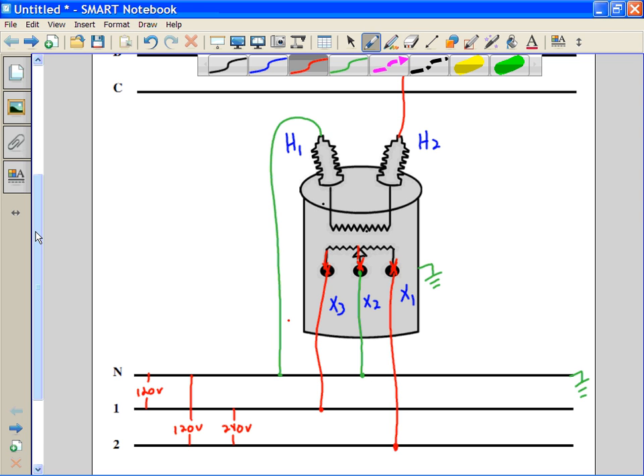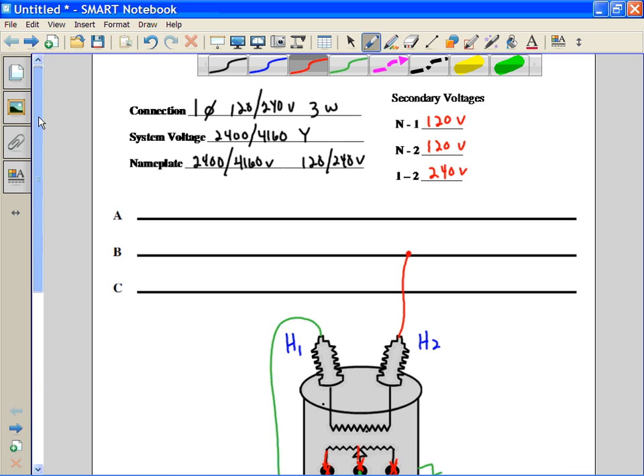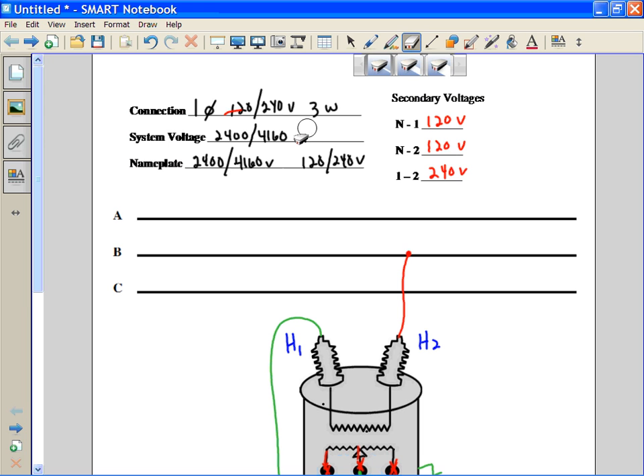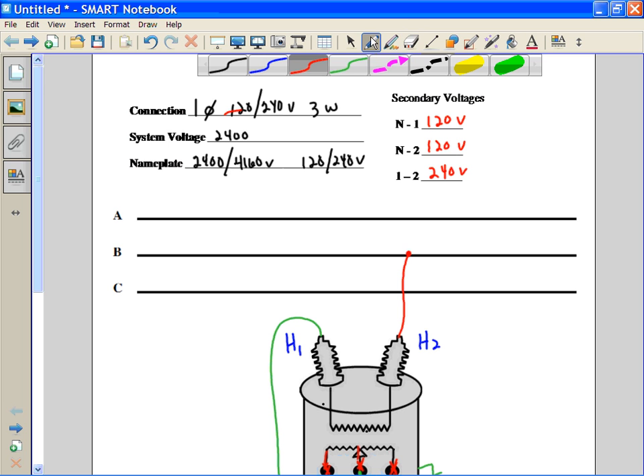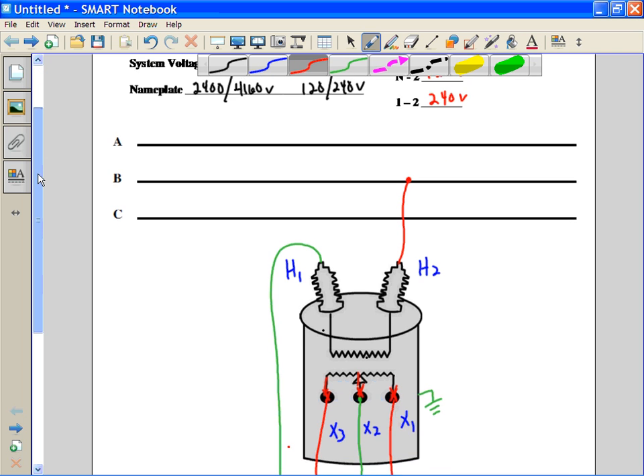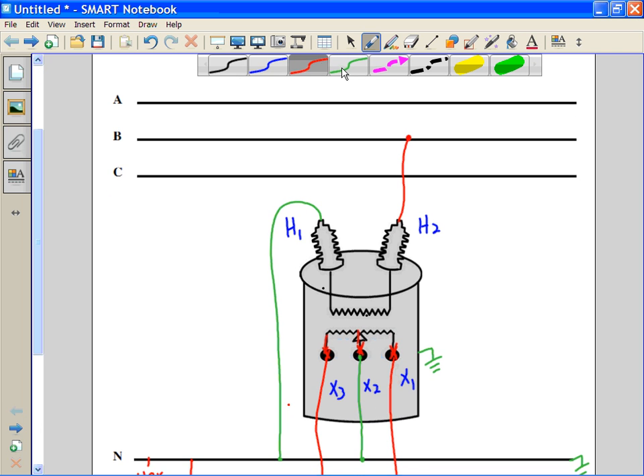Now let's take this one a step further and change the connection so that instead of being a Y connection, we're going to have to connect this to a delta circuit. So if we have a 2400 volt delta system instead of a Y system, we have to change our connection a little bit on the primary side. Nothing's going to change on the secondary side, and since 2400 volts is the only voltage on the delta system that's going to be available to us, we can use the same transformer in this case. What we have to do differently is how we make our primary connection. That will be the only thing that will change.